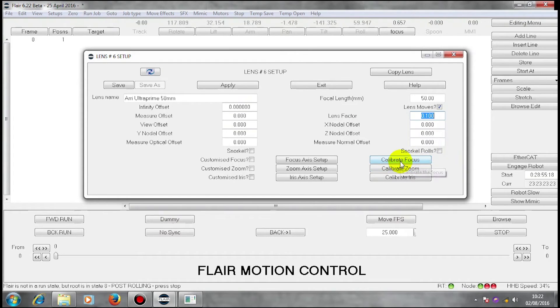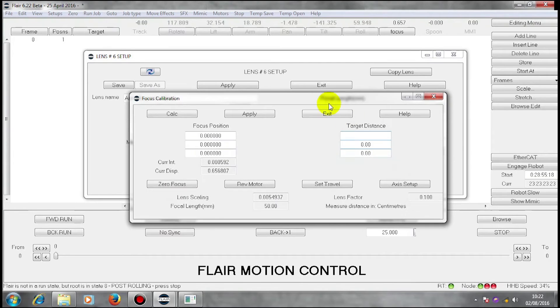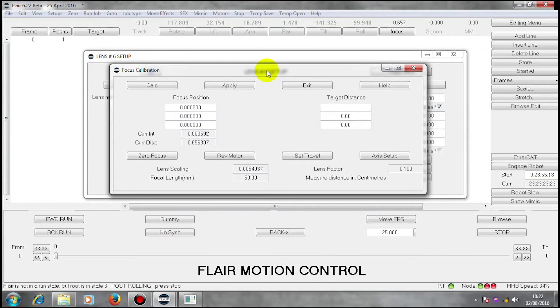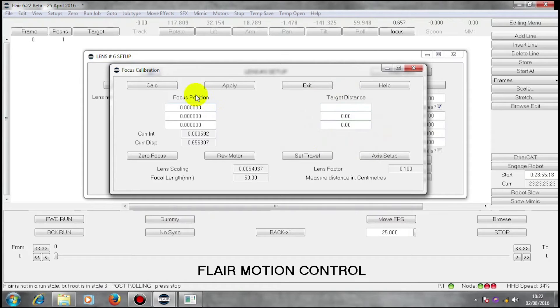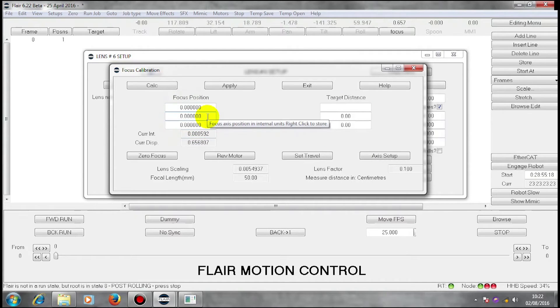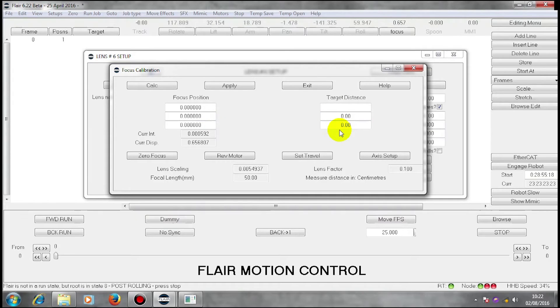I can now open this box called calibrate focus. In this calibrate focus box, I have three target distances and three focus positions. These are readings from the motor which is in mesh with the gears on the lens. These are the target distances as marked on the marks on the lens.